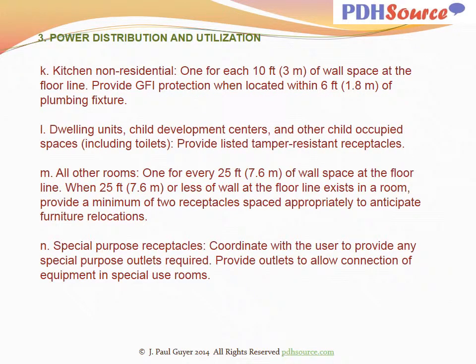Kitchen, non-residential, one for each 10 feet of wall space at the floor line. Provide GFI protection when located within 6 feet of plumbing fixture. Dwelling units, child development centers, and other child-occupied spaces, including toilets, provide listed tamper-resistant receptacles.